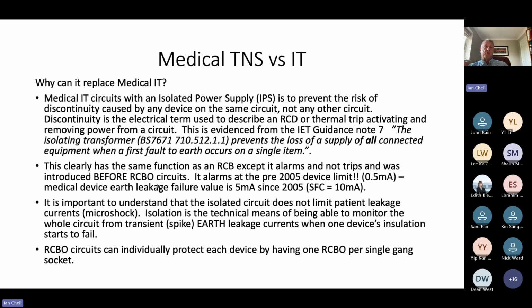And as I mentioned before, you have a completely different level of medical device safety, and we have our RCBOs, okay? And we also have the supplementary equipotential bonding to support these design features of a medical device. So the isolation is only the technical means of being able to monitor the whole circuit from one transient spike when one device's insulation starts to fail. So RCBOs can individually protect each device by having one RCBO per single gang socket.